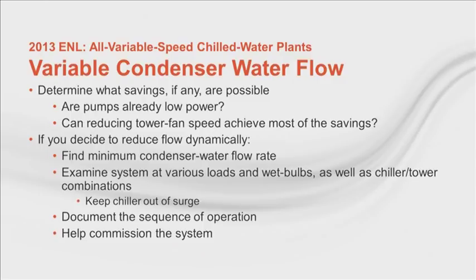But if you do decide to reduce flow, there are limits to consider, including the minimum chiller condenser water flow rate, not only from the chiller's perspective, but also from the tower's and the pump's perspectives. As you examine combinations of load and flow rate, you'll need to identify limits that keep the chiller out of surge. Documenting the sequence of operation and assisting with the commissioning of the system should be required of anyone dynamically modifying the condenser flow rate.